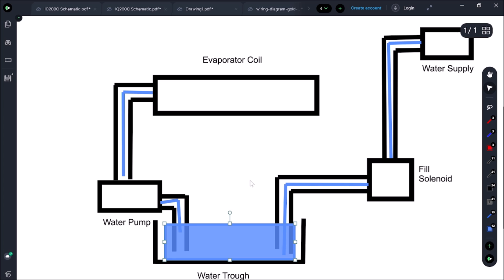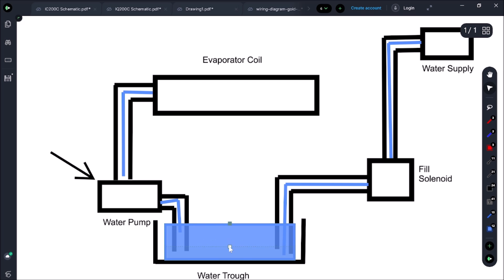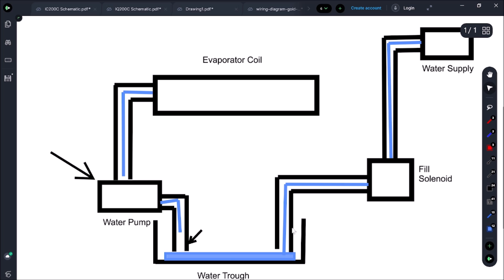At the current moment I know I have water in the trough and there's enough water for this pump to run. But now the question is is there enough water in the trough? If water gets below this line right here you can see the pump can't pick it up. So how do we know if our water level's high enough in the trough? There's actually an overflow in this trough. That's the best way for us to really test it.